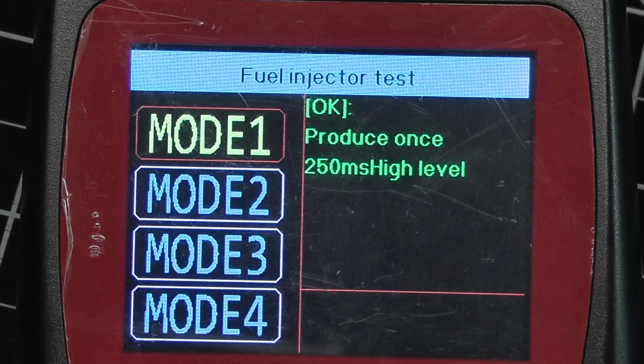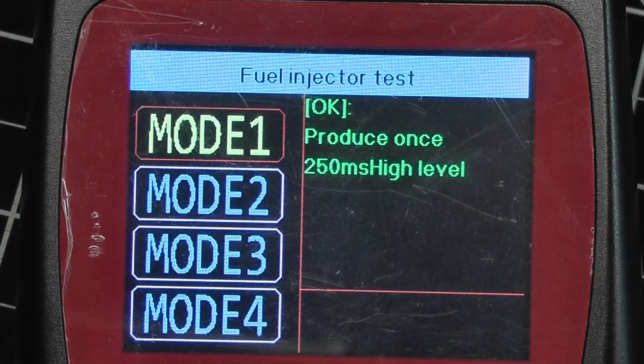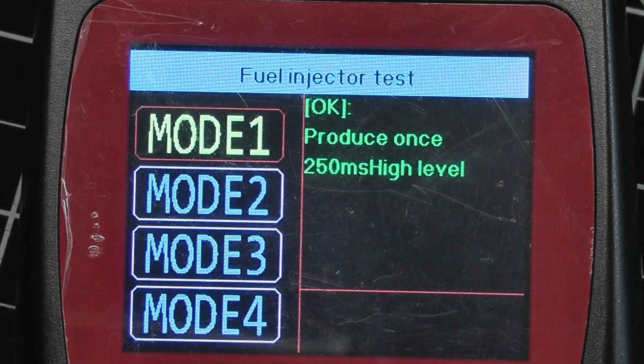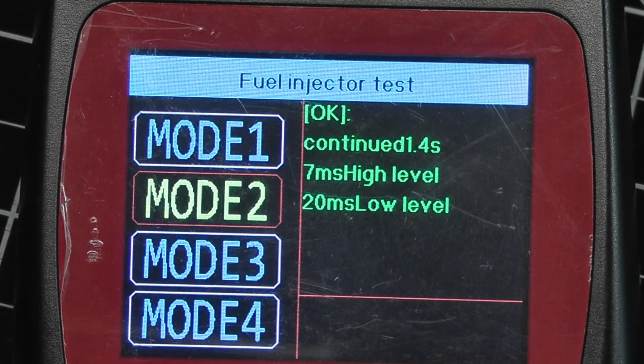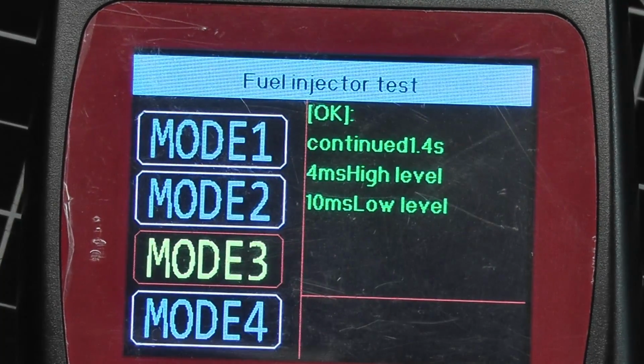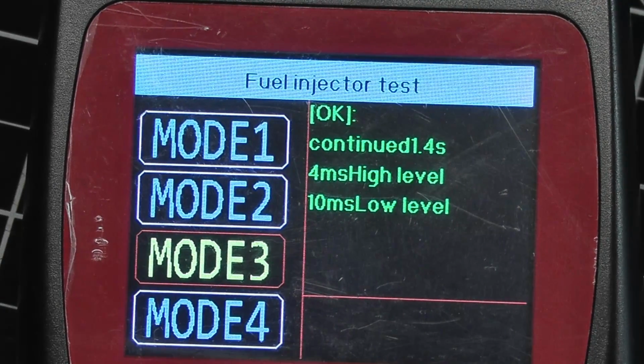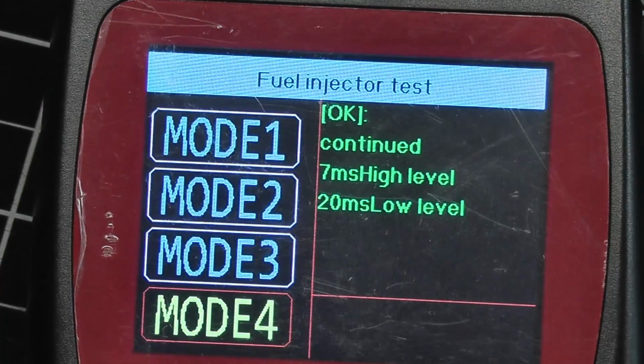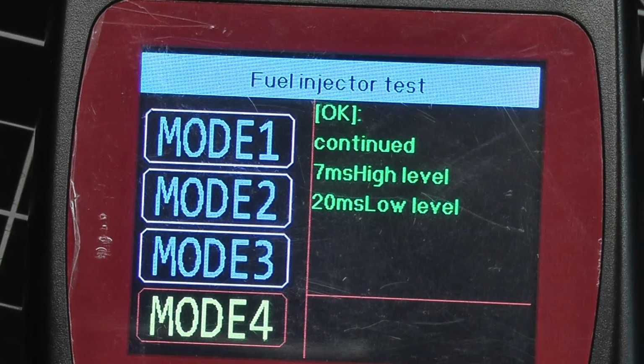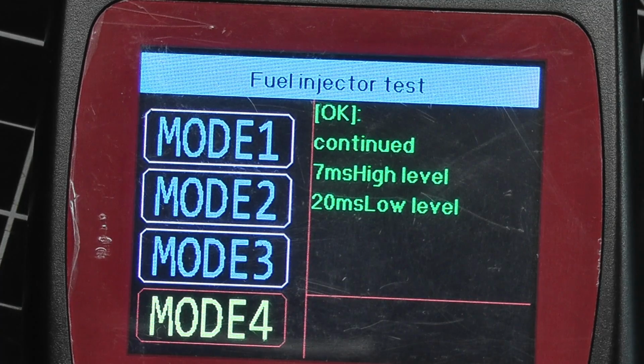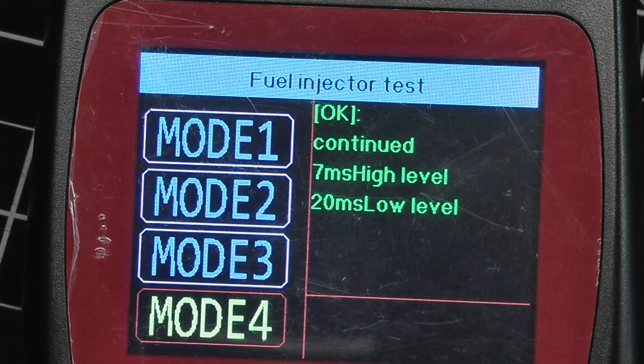So there's 4 modes for the injector testing. Mode 1 will output 1 pulse, so 1 shot if you like, at 250 milliseconds, and then it steps down. Mode 2 will output 50 pulses at 7 milliseconds, and mode 3 is 100 pulses at a width of 4 milliseconds. And then mode 4 is continuous, so it's continually pulsing at a rate of 50 pulses in 1450 milliseconds, and every one of those pulses is 7 milliseconds.